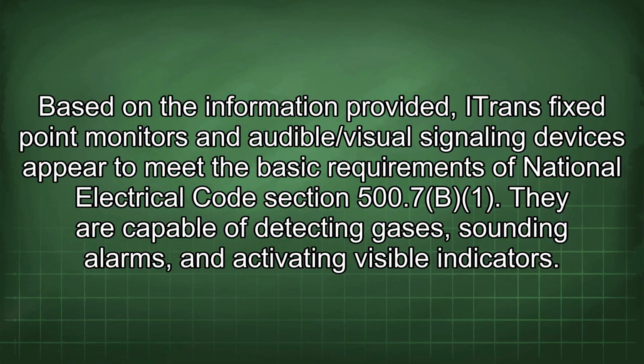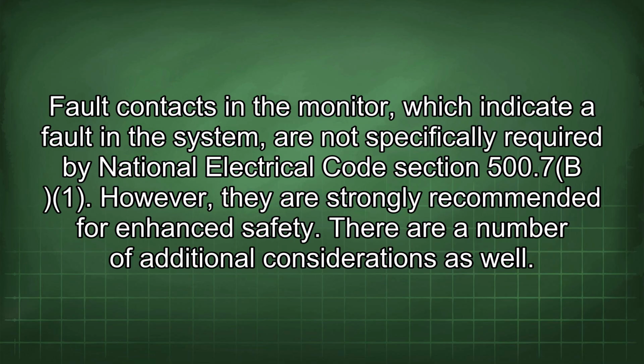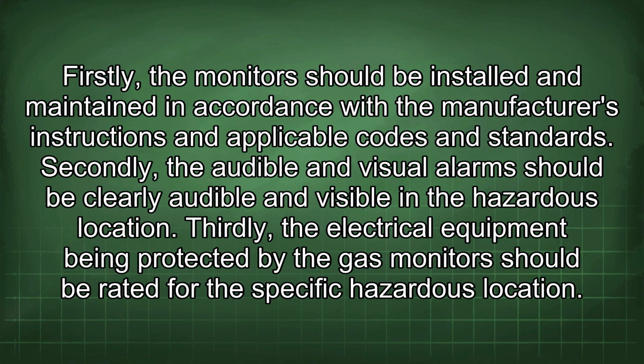They are capable of detecting gases, sounding alarms, and activating visible indicators. Fault contacts in the monitor, which indicate a fault in the system, are not specifically required by National Electrical Code Section 500.7(B)(1). However, they are strongly recommended for enhanced safety. There are a number of additional considerations as well. Firstly, the monitor should be installed and maintained in accordance with the manufacturer's instructions and applicable codes and standards. Secondly, the audible and visual alarms should be clearly audible and visible in the hazardous location. Thirdly, the electrical equipment being protected by the gas monitor should be rated for the specific hazardous location.